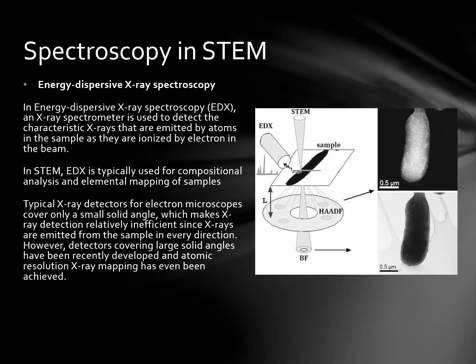Energy dispersive X-ray spectroscopy, EDX, uses an X-ray spectrometer to detect the characteristic X-rays emitted by atoms in the sample as they are ionized by electrons in the beam. In STEM, EDX is typically used for compositional analysis and elemental mapping of samples. Typical X-ray detectors for electron microscopes cover only a small solid angle, making X-ray detection relatively inefficient since X-rays are emitted from the sample in every direction. However, detectors covering large solid angles have been recently developed, and atomic resolution X-ray mapping has been achieved.